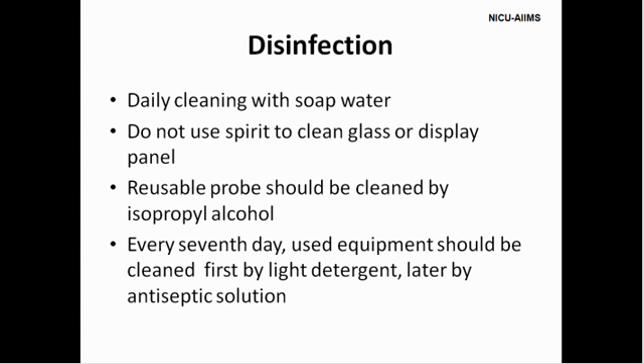What to do for disinfection? Daily cleaning with a cloth soaked in soap and water. Spirit not to be used either to clean the glass or the display panel. Reusable probe to be cleaned by isopropyl alcohol, and every 7th day the used equipment should be cleaned first by a light detergent and then by an antiseptic solution. To remove a side panel, lower the side panel, press the end pins in and lift the side panel out. To replace, follow the similar procedure.